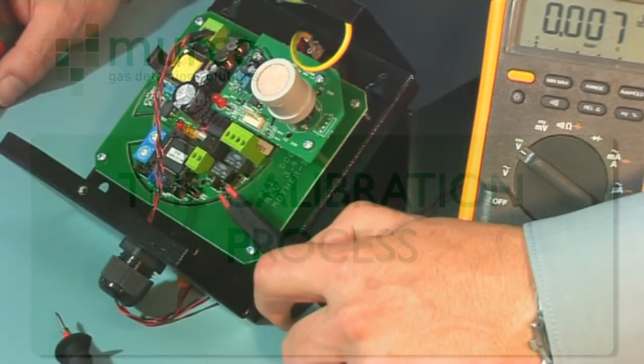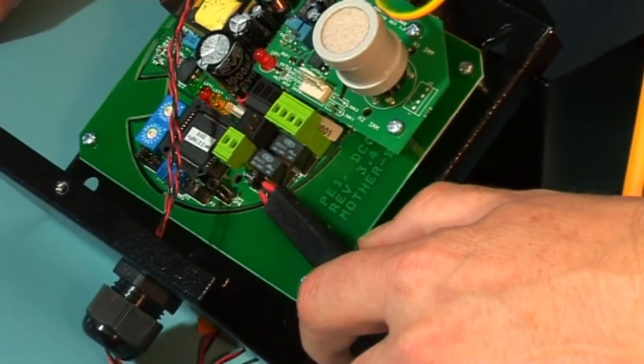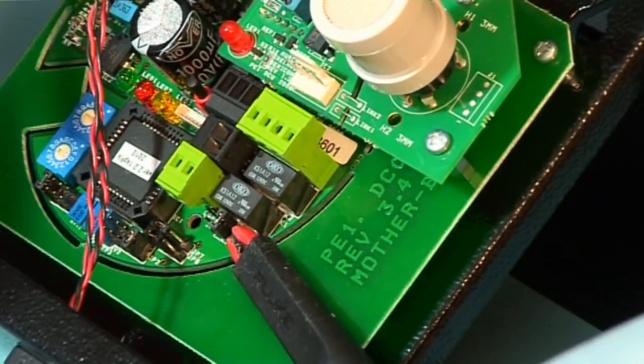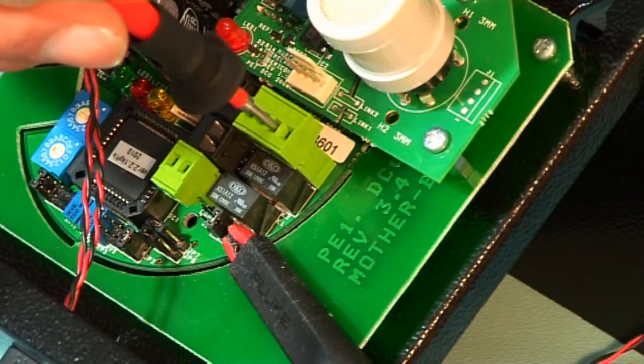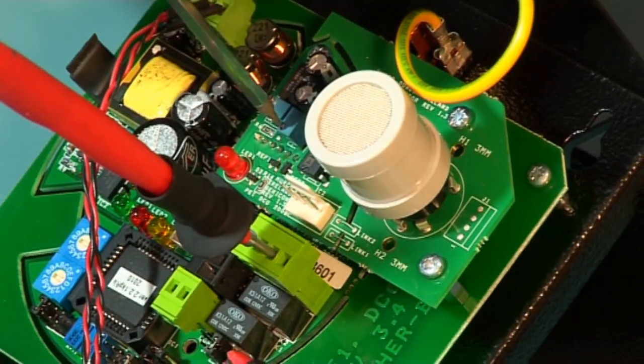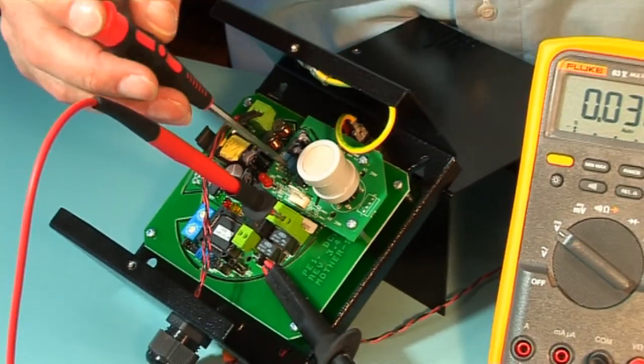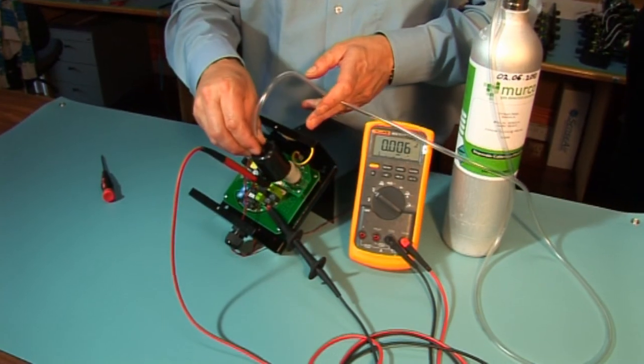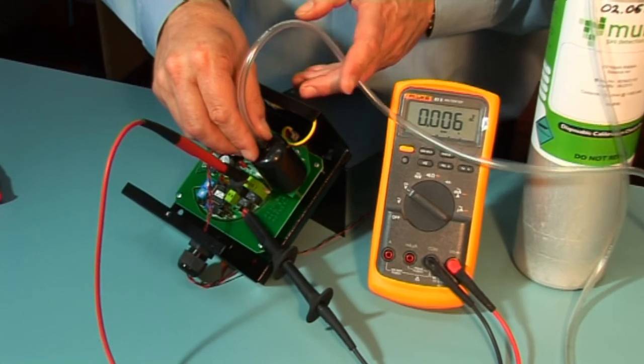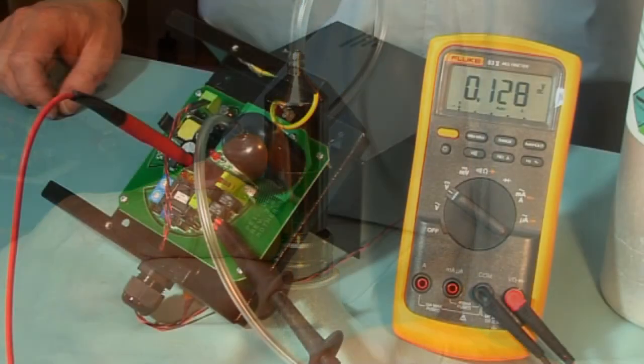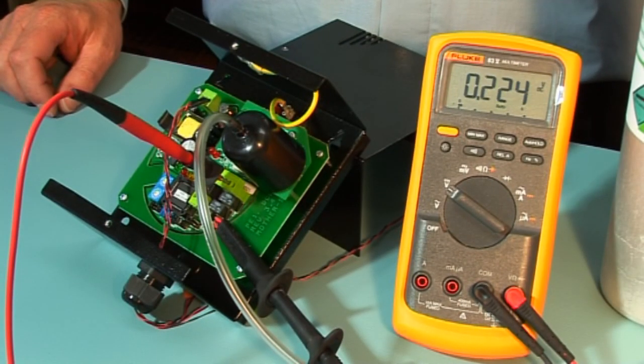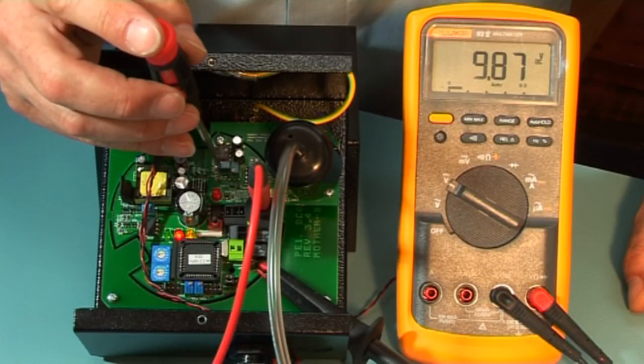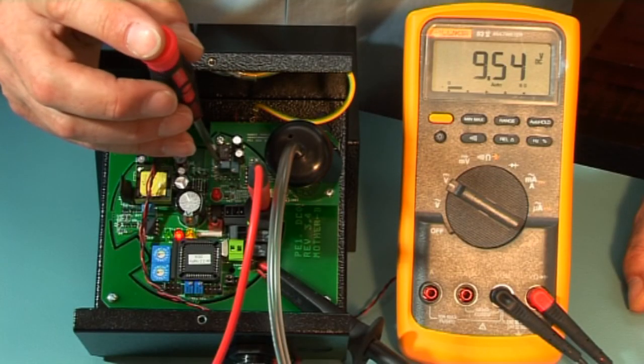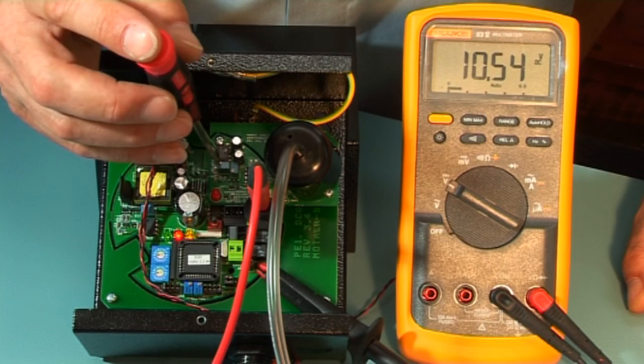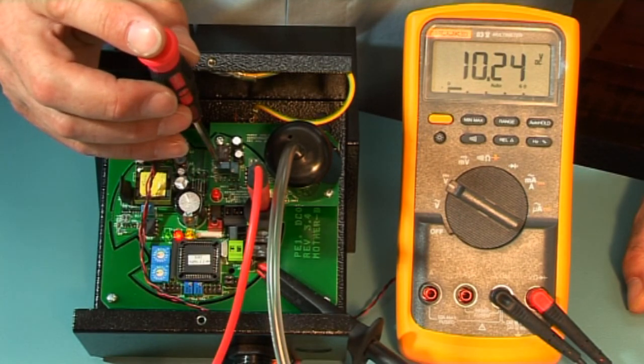Connect between TP0 and pin 3 on CON3 with your known target gas of specified range. Adjust RV2 for 0 volts in clean air. Expose the sensor by introducing gas to the sensor here, and you should see the voltage increase. Once the voltage stops climbing and stabilizes, then adjust the voltage output to 10 volts using RV1. The ST-IAM will now be in alarm and relays should activate.